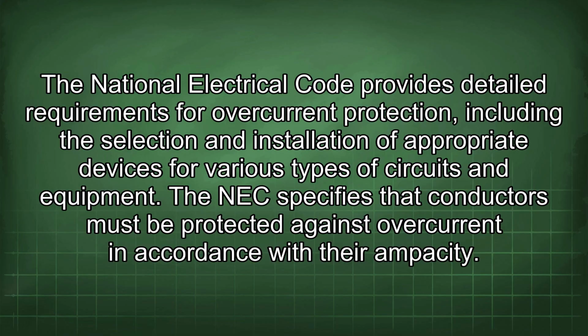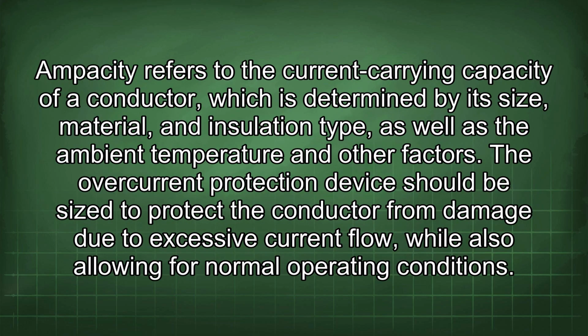The NEC specifies that conductors must be protected against overcurrent in accordance with their ampacity. Ampacity refers to the current carrying capacity of a conductor, which is determined by its size, material, and insulation type, as well as the ambient temperature and other factors. The overcurrent protection device should be sized to protect the conductor from damage due to excessive current flow, while also allowing for normal operating conditions.